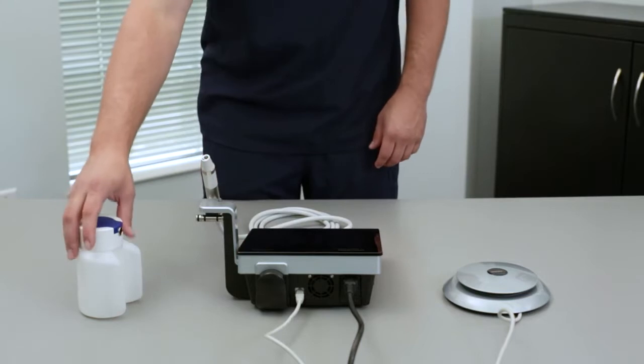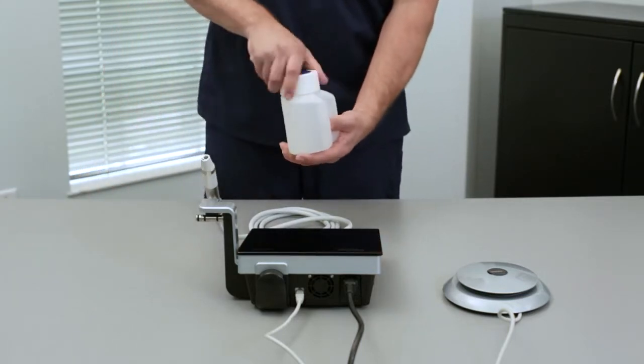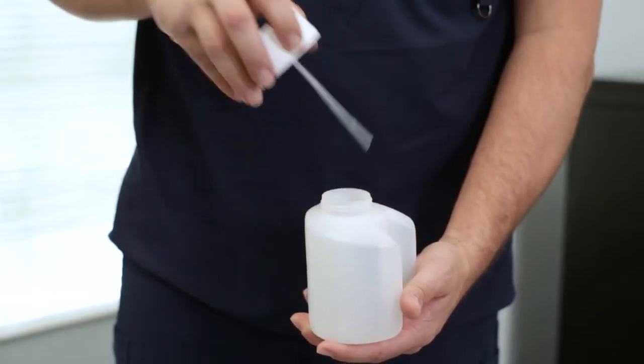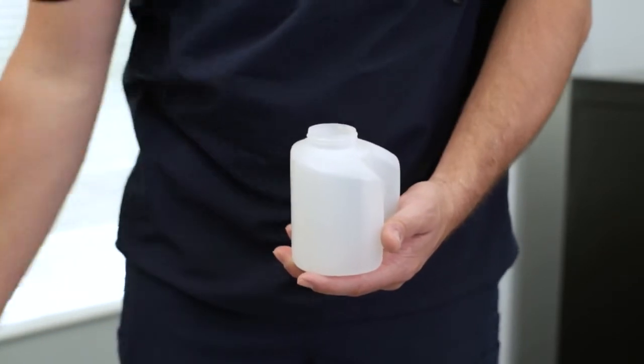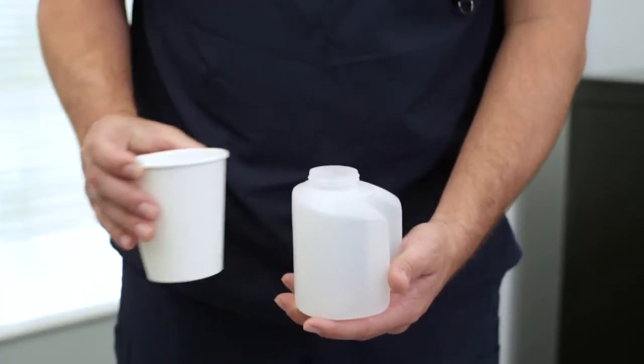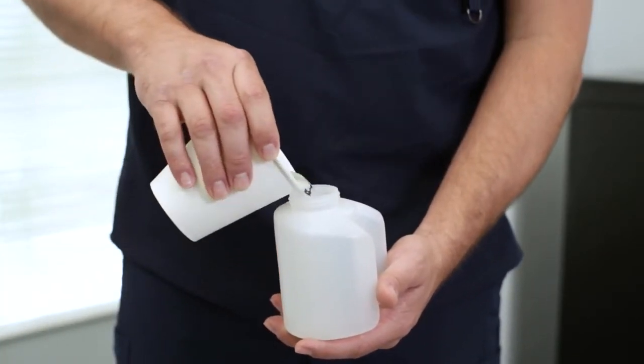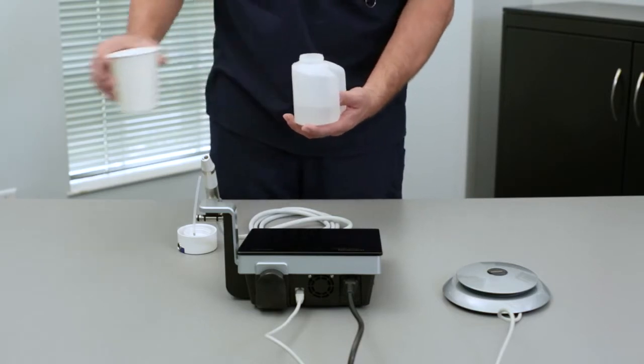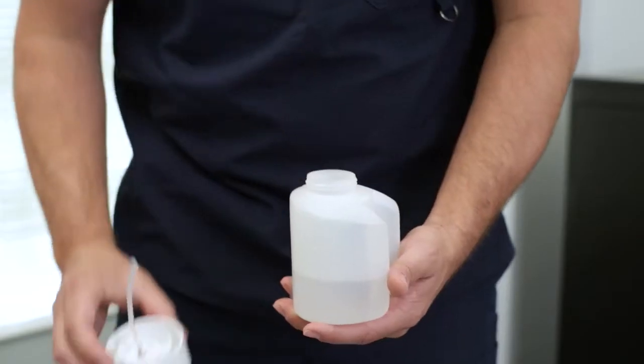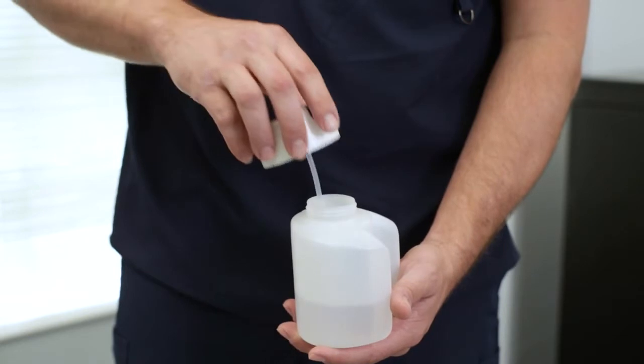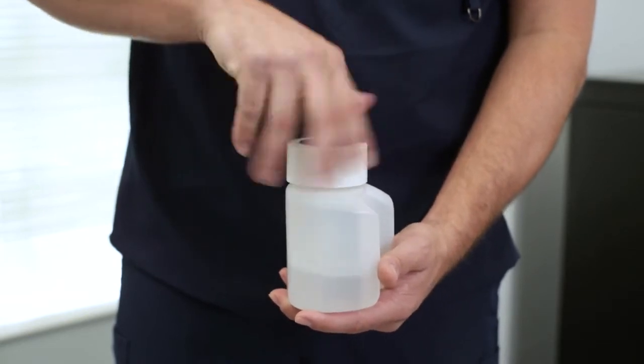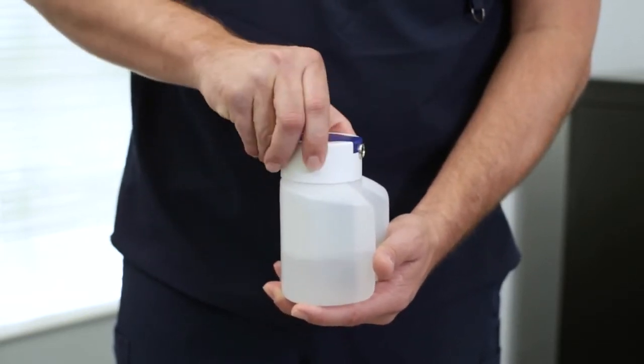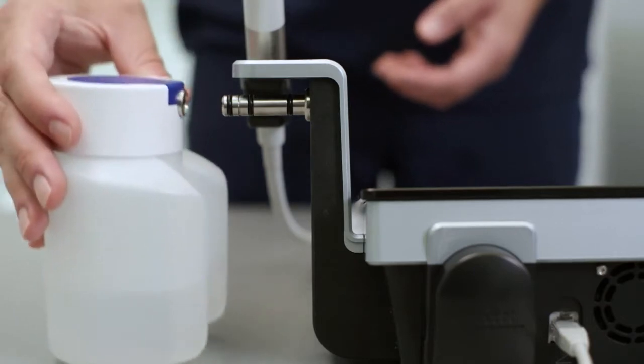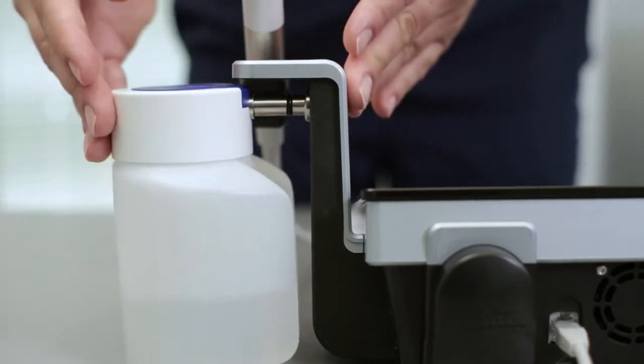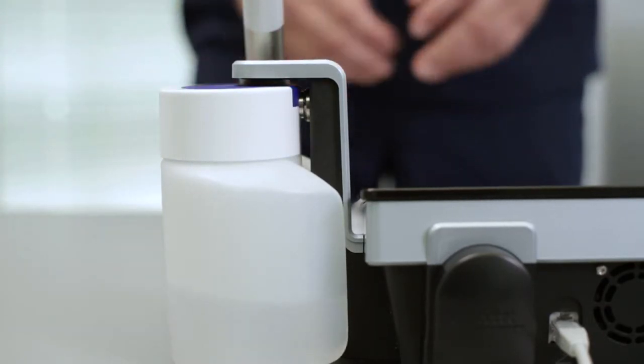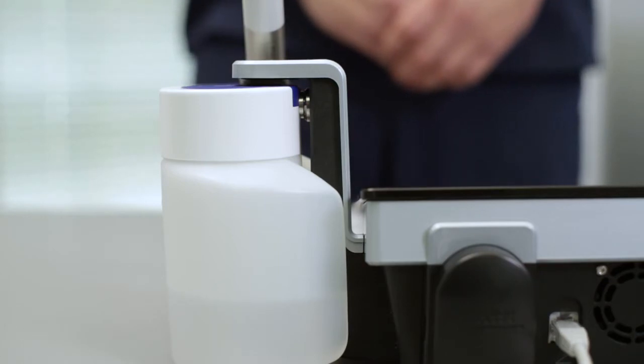Now that the handpiece is connected, unscrew the lid from one of the irrigation bottles and fill the bottle with the desired solution. Check that the hose of the lid is correctly installed, and then screw the lid back onto the bottle. Next, attach the bottle to the device by gently sliding it over the device coupling. To prevent the device from moving or sliding during installation, it is advised to place one hand behind the connection as you are attaching the irrigation bottle. The device is now fully assembled.